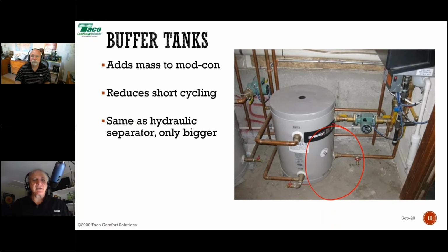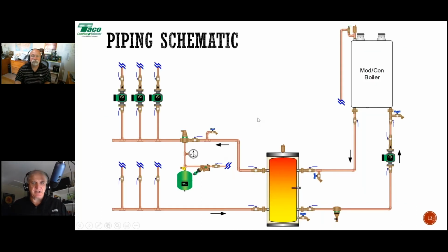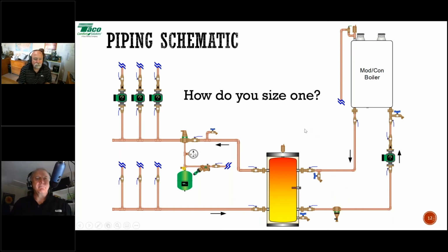The question always comes in, how do we size one of these things? Here's your piping schematic, and it's the same as a hydraulic separator. But the question is, how do we know what size buffer tank to use? And to me, this isn't a pie in the sky thing, or something people are never going to really use. If you have a system where the smallest zones are smaller than the lowest firing rate of the boiler, a buffer tank isn't a nice thing to do. To me, it's standard equipment. You've got to do this to prevent that boiler from short cycling.